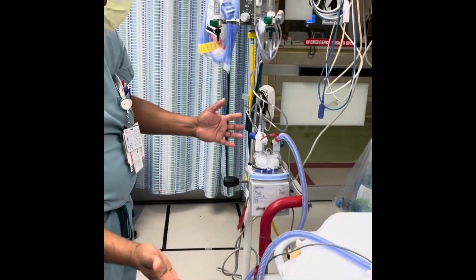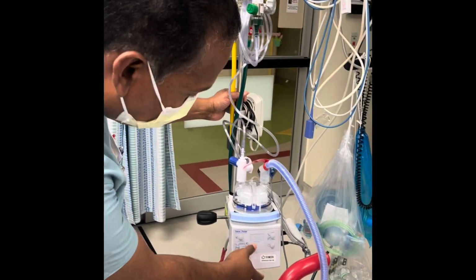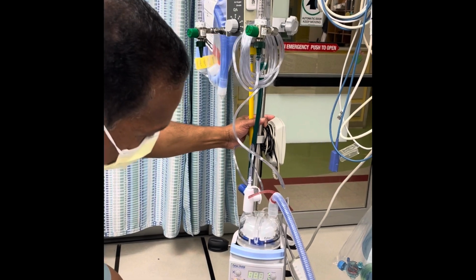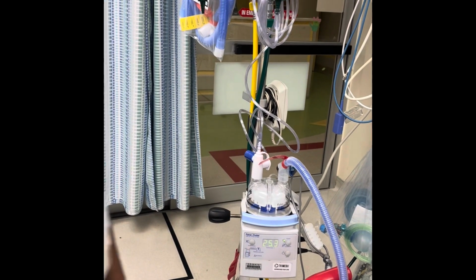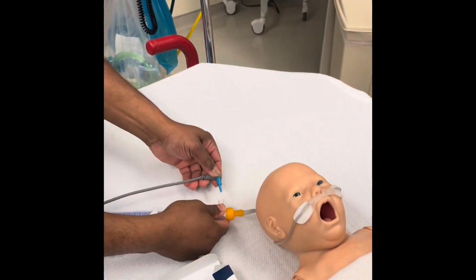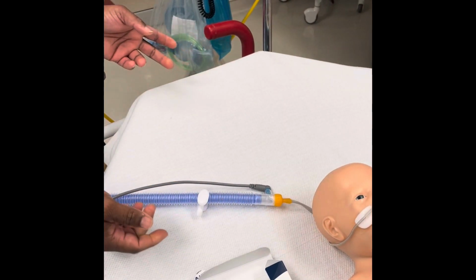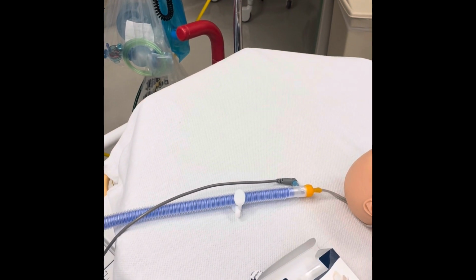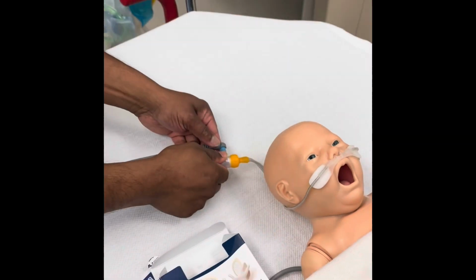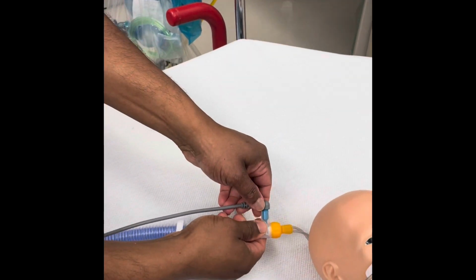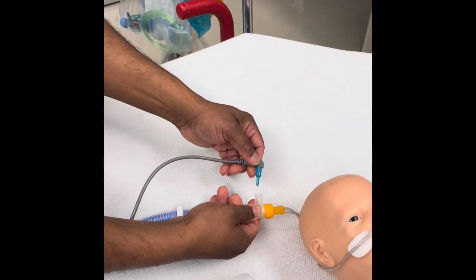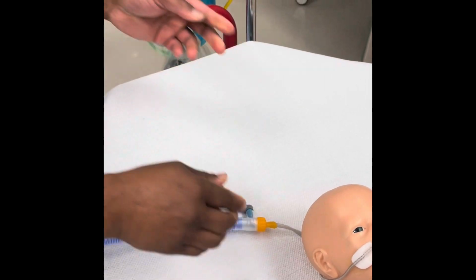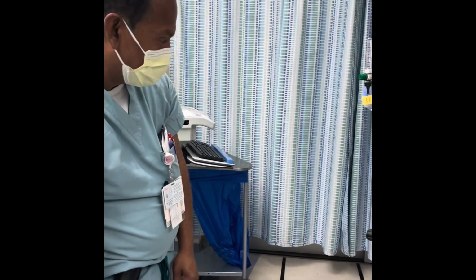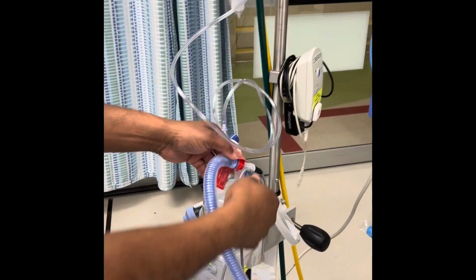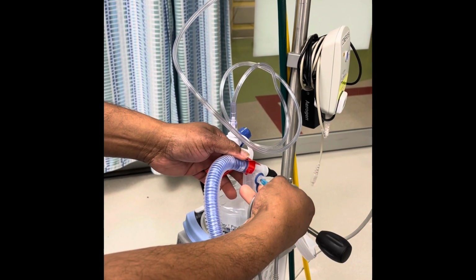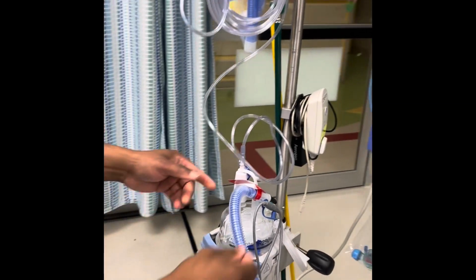The most common troubleshooting we have is when we turn the humidifier on, it starts alarming. That's because sometimes the temperature probe may be loose. Maybe it came off, so outside air gets into the system, and the temperature reading may be a little bit higher on the chamber. So make sure this is pushed in tight. If you tighten it, you will hear the alarm stop. When the temperature probe comes off, usually no flow is delivered to the patient. Everything will be escaping. The other area for disconnection is over here by the chamber. All you have to do is just push it in.